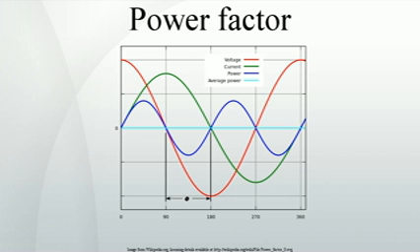Power factor correction of linear loads. A high power factor is generally desirable in a transmission system to reduce transmission losses and improve voltage regulation at the load. It is often desirable to adjust the power factor of a system to near 1.0. When reactive elements supply or absorb reactive power near the load, the apparent power is reduced.